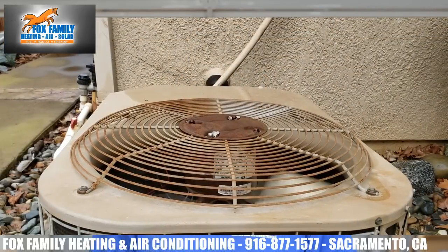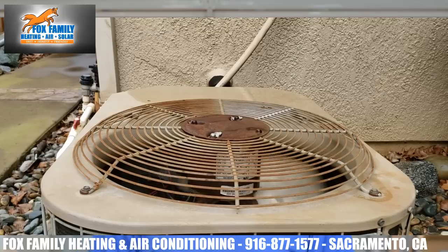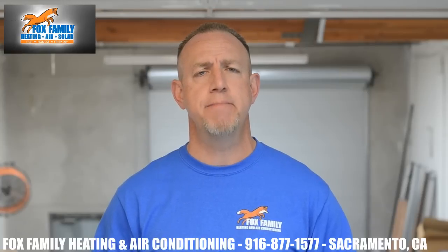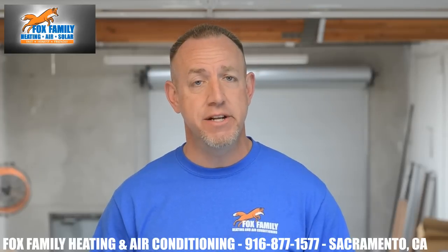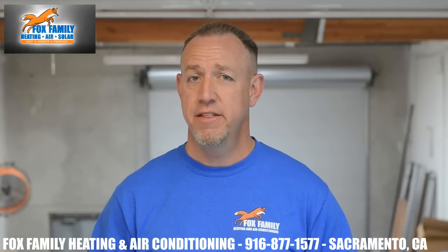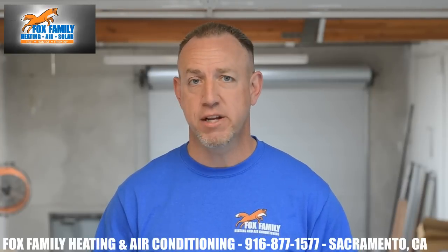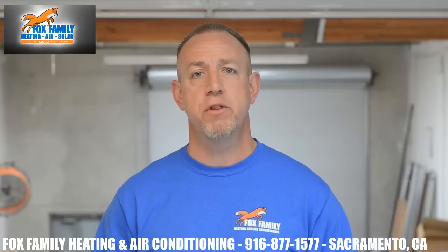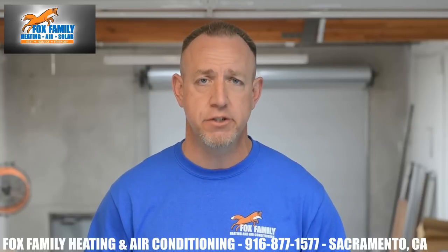Another time we might have to replace the part making the noise is on the condenser fan motor — that's the fan blade you've probably seen spinning on the top of your AC when it's running. I've come out on a house where this motor was making a high-pitched whistling noise. After isolating the noise to the motor, I found that every AC motor has ball bearings that help the motor shaft spin, but these bearings are sealed and can't be accessed to lubricate them, which would likely solve the problem. So in this case, the motor has to be replaced. Finding the right motor can be tricky, so it's probably best to let a qualified technician do it.